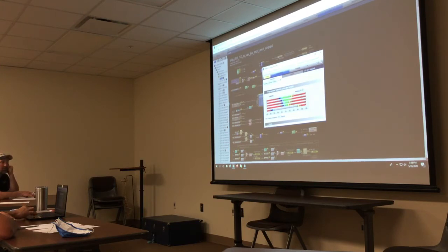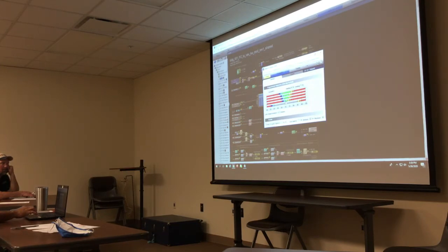So when I make changes, I click on the green bar right here, this one, and I type in the changes I want to make. The demand are those other 3 bars. What demand is, as the system decides if it needs to relax your set point, it goes to different demand levels. The first one, demand 1, relaxes 1 degree. Demand 2 relaxes 2 degrees. Demand 3 relaxes 4 degrees.